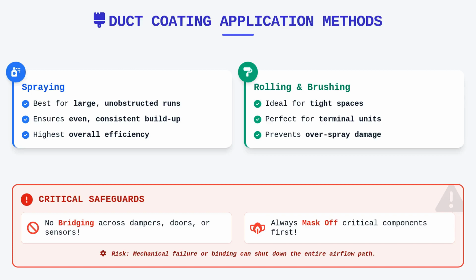You should never apply sealants in a way that creates bridges across moving parts like dampers, access doors, or delicate sensors. If a sealant cures across a damper blade and the actuator attempts to cycle, you risk mechanical failure or binding that could shut down the entire airflow path. Always mask off these critical components before you even begin the application process to avoid these complications.